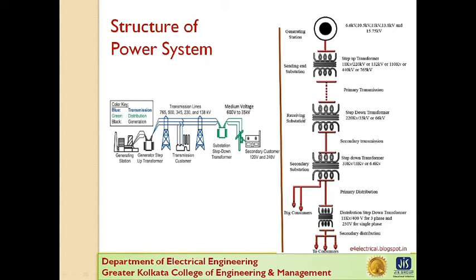At the receiving station, the voltage is reduced to 33 kV or 66 kV by a step-down transformer. From this station, electric power is transmitted at 33 kV by a three-phase three-wire system to various substations located at strategic points in the cities. This forms the secondary transmission. Next, primary distribution. The secondary transmission line terminates at the substation, where the voltage is reduced from 33 kV to 11 kV or 6.6 kV by a three-phase three-wire system.